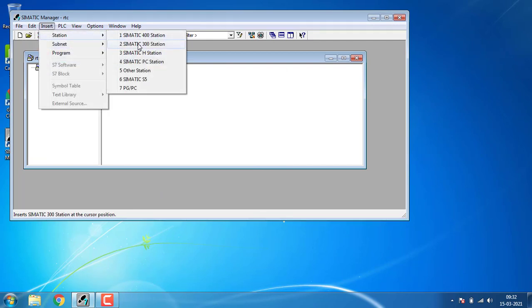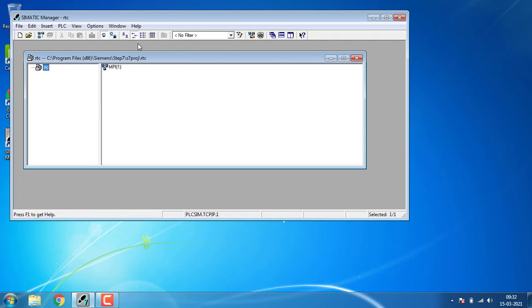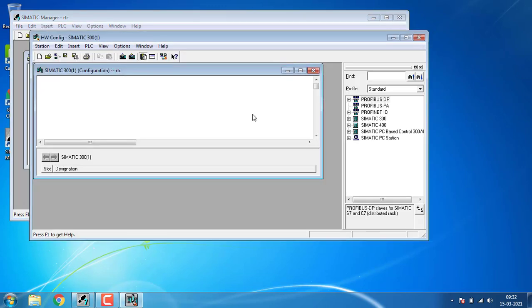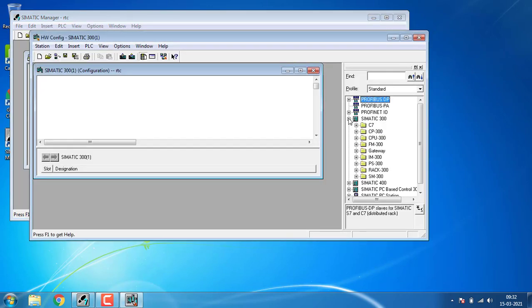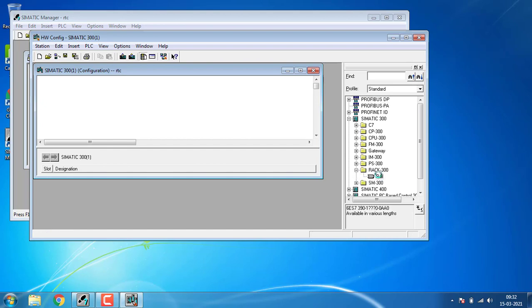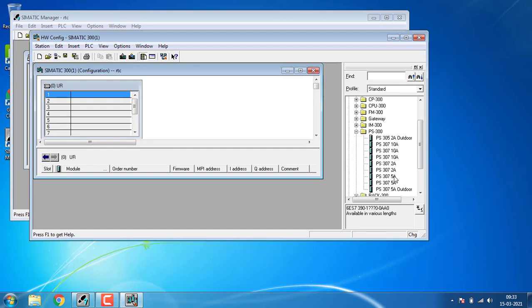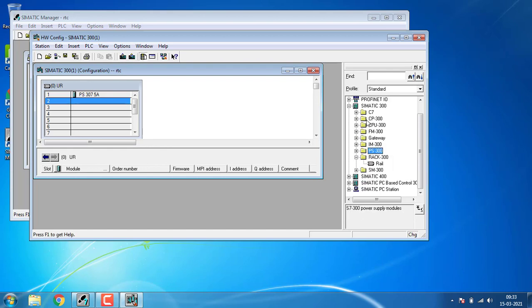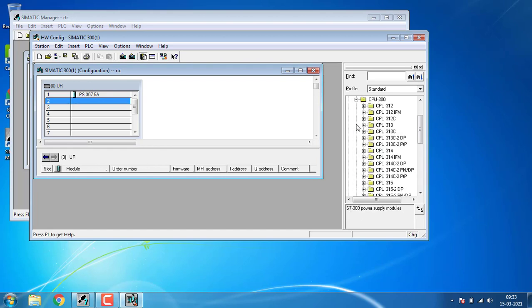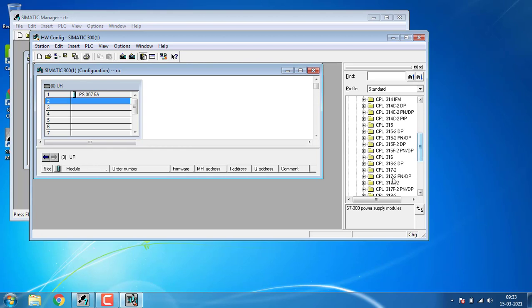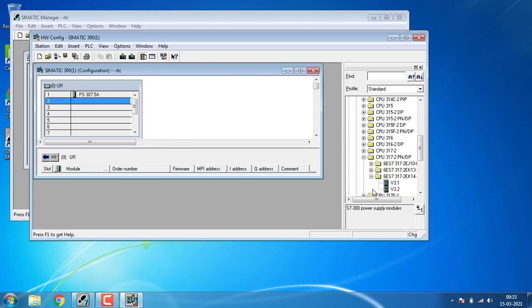Then I'm going to insert a new SIMATIC 300 station. In the station, I'm going to set up the hardware first. In the hardware configuration, I'm going to add the SIMATIC 300 station. Go for the rack and put the rail first, then go for the power supply PS 300. I'm using a 5 amps power supply. Then I'm going to set up a CPU 300, using the CPU 317-2 PN/DP, the third version V 3.1.